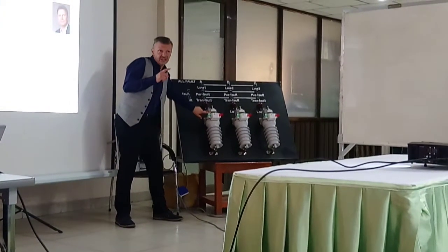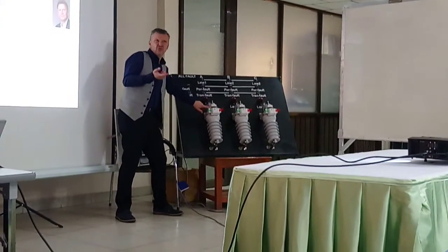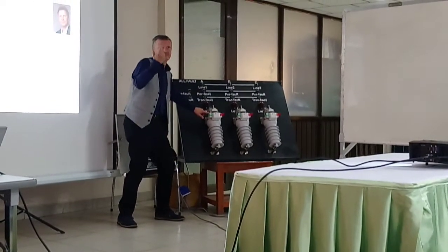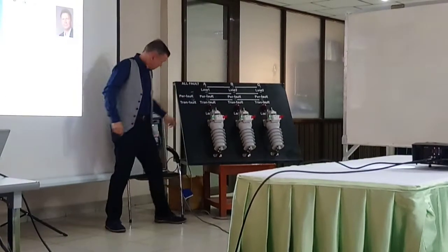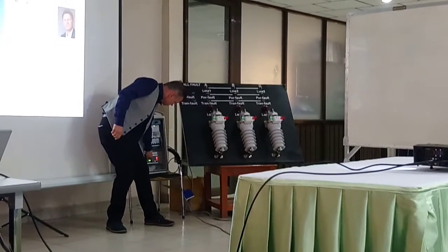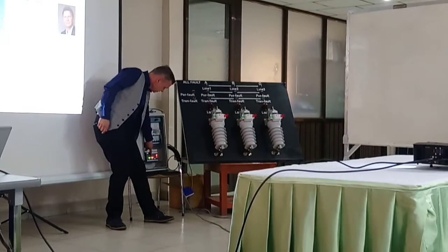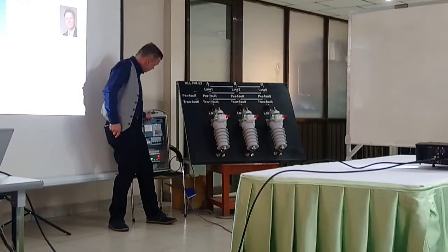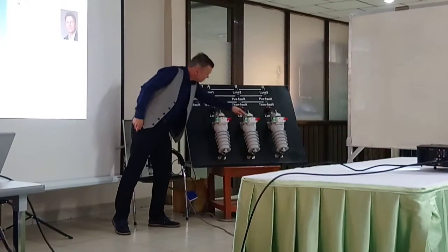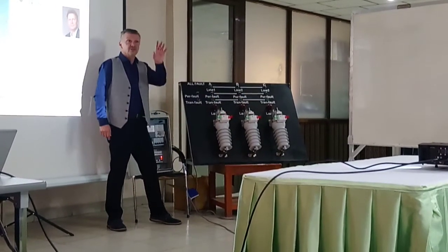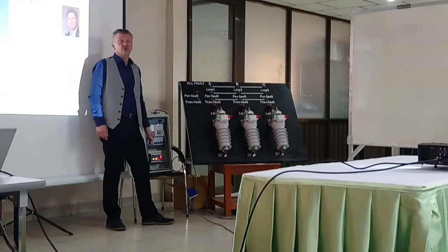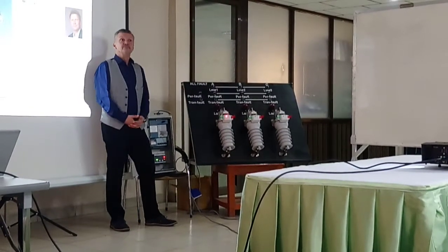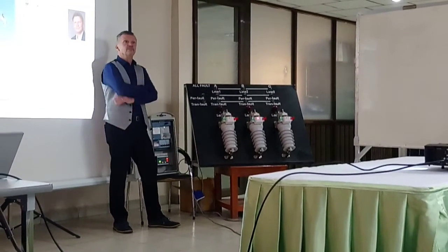By the way, it's a reflecting material. If it is dark or the sun is there, use a torch, and then it starts to reflect, and it's easier to see. If you use that one here, close, it starts here. I received the command. I will talk with wireless radio to those devices. All three understand. It's time to step back for the operator, and the 60 seconds run, and then it's okay. Then the Fuse Saver will close synchronously.